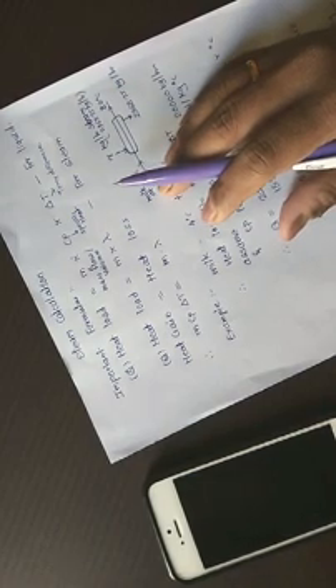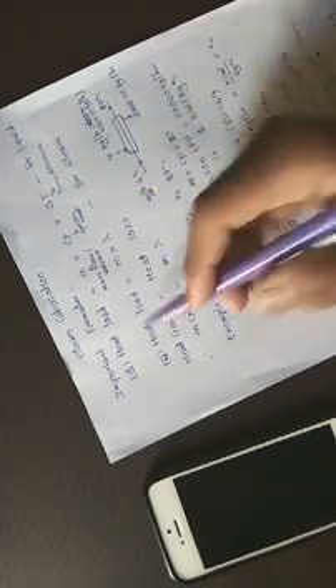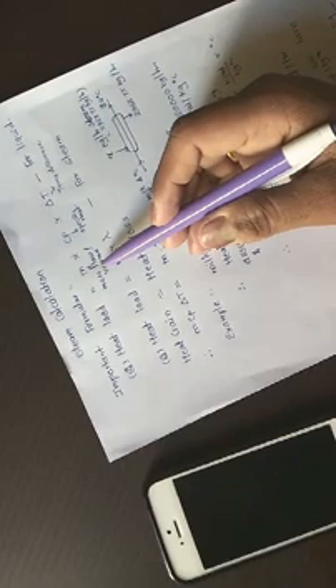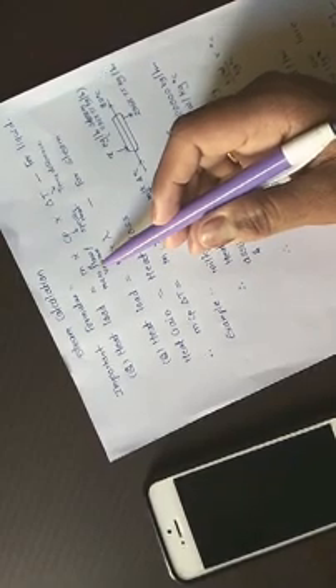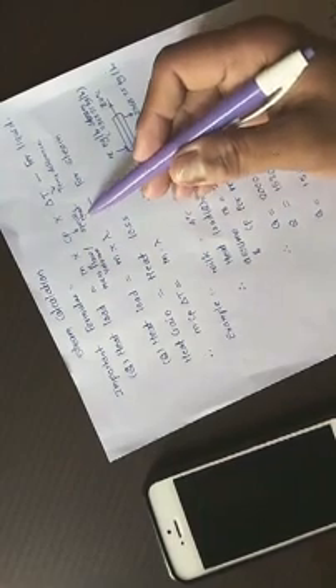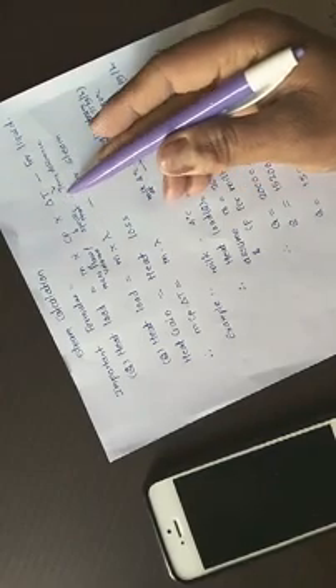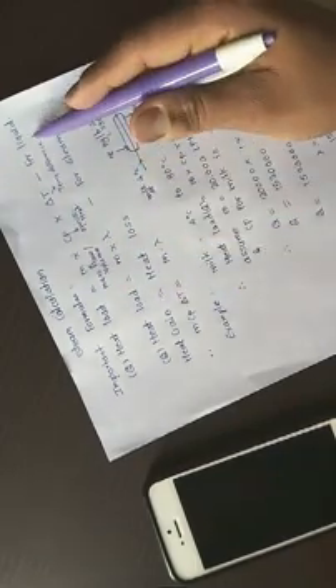So first is the heat load calculation from the product side. For that you have the formula Q, that is heat load, is equal to M Cp delta T. What is M? M is the mass flow rate or volume which you have to heat. For mass flow rate, you should have the unit in kg per hour. If you have flow rate in liter per hour, then you should convert it into kg per hour. Then Cp is the specific heat for that particular product, let's say water or milk. Then delta T means temperature difference. So this is for the product or liquid side.